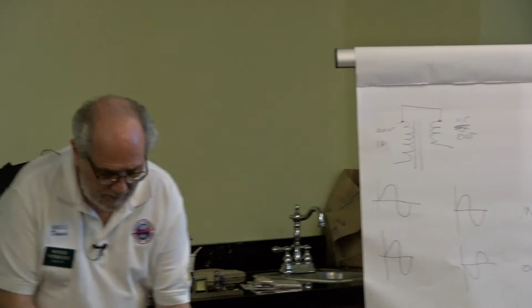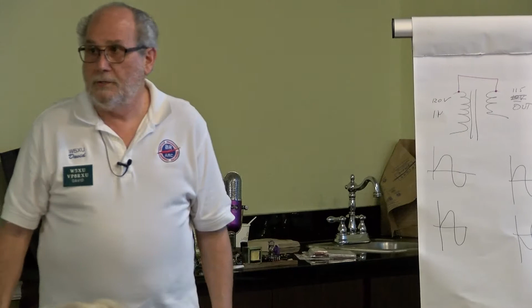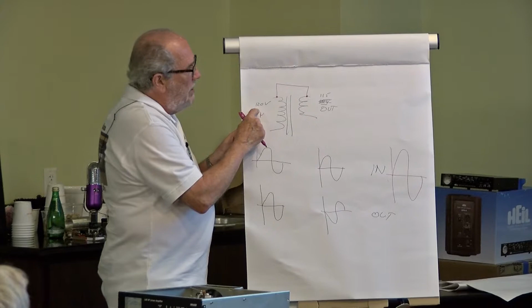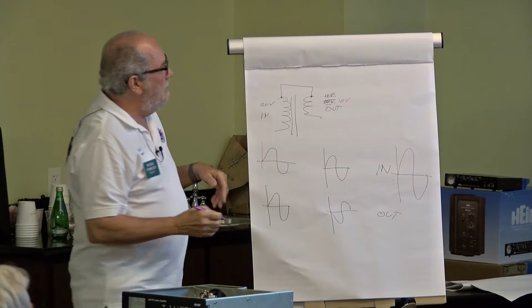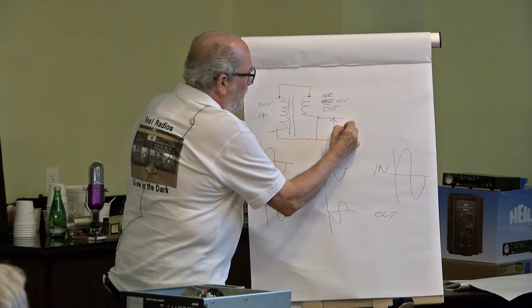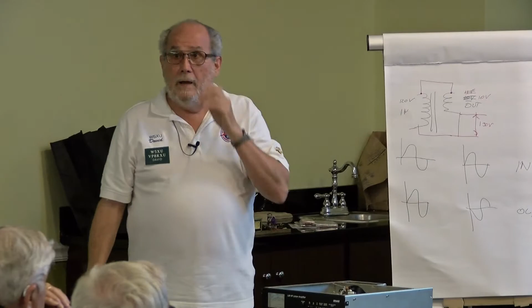If that's the case, with the transformer connected this way, that's called a boost connection—I'm basically adding the voltage on the primary to the voltage on the secondary. So if I go back to our original 120 volts, what I measure from here to here is 130 volts. It is a boost transformer. For our purposes, that connection isn't going to help us—we're heading in the wrong direction.